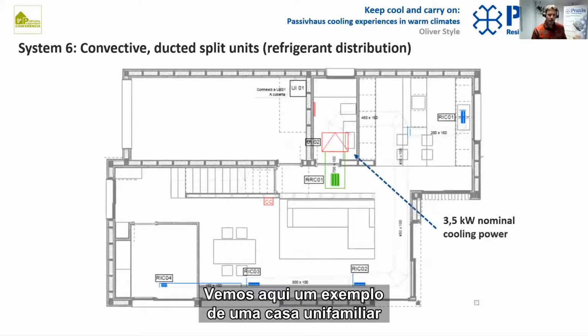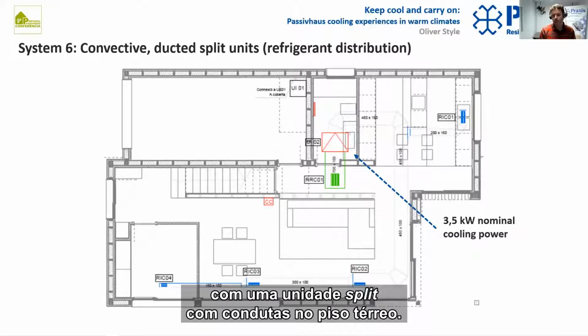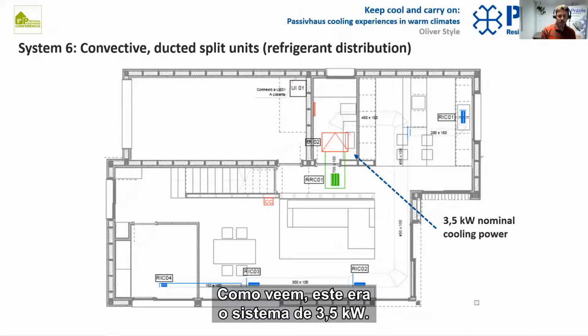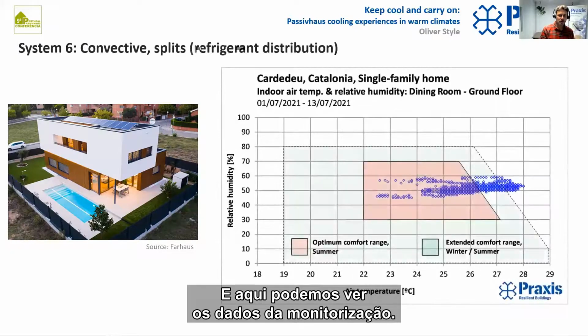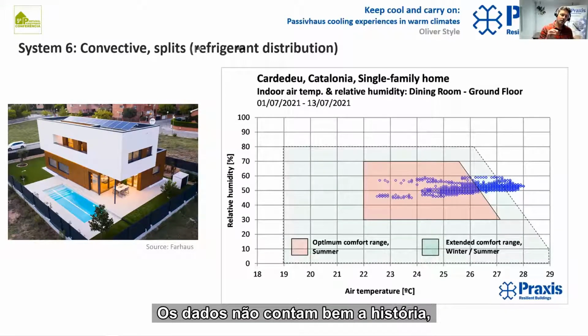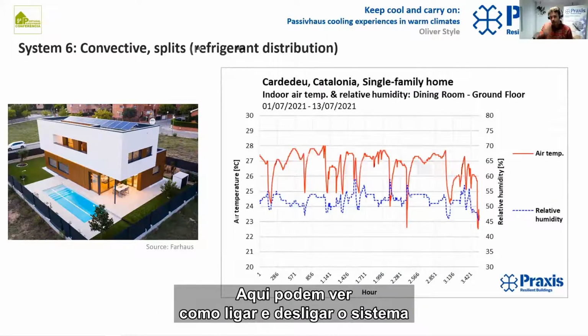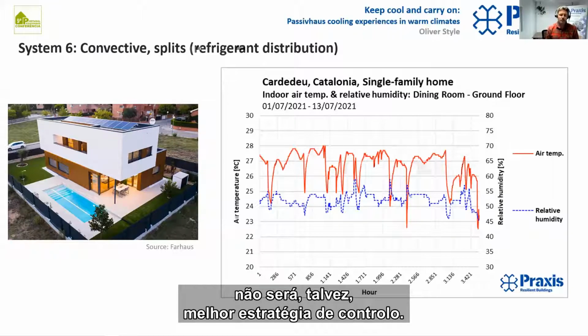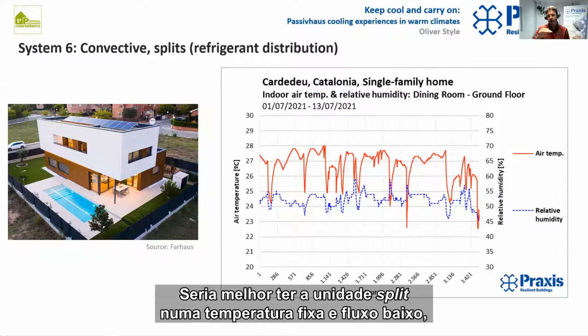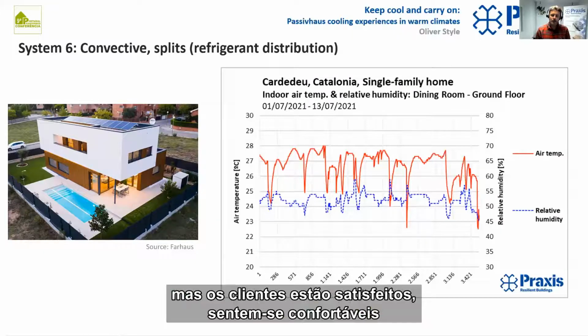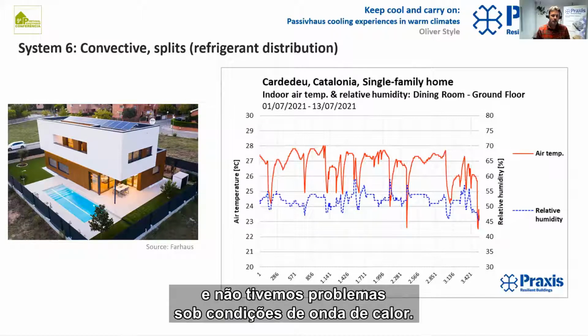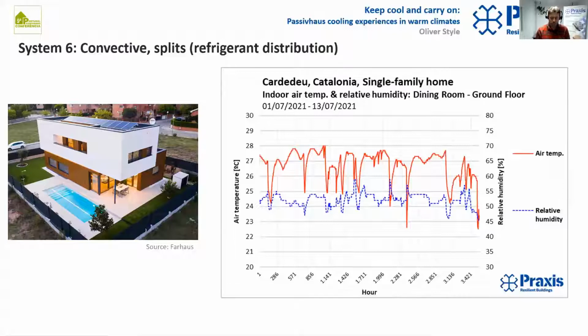So here we're looking at an example of a single-family home with a ducted split unit on the ground floor. As you can see here, this was a 3.5 kilowatt system. And here we can see monitored data. So the monitored data doesn't tell all the story here, mainly because the users were out of the house when the temperatures are higher, and then they come in and turn it on. Here you can see when they've come in and turned the system on and off, not at all an optimum control strategy. It would be best to run the split unit at a fixed temperature setting and low flow. But the clients are happy. They're very comfortable. Energy use is low, and under heat wave conditions, they've had absolutely no problems.